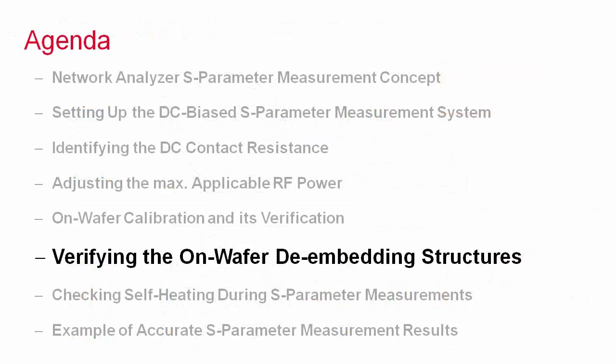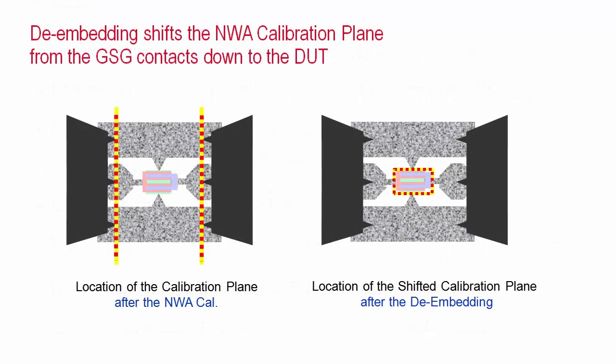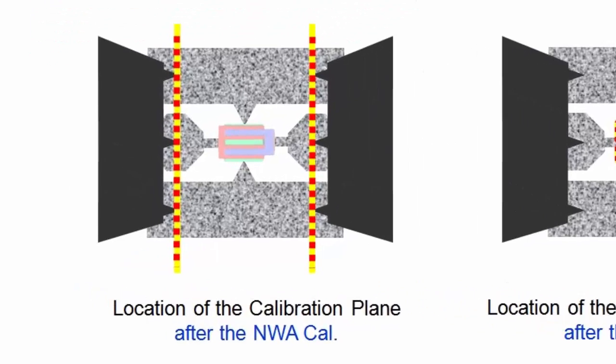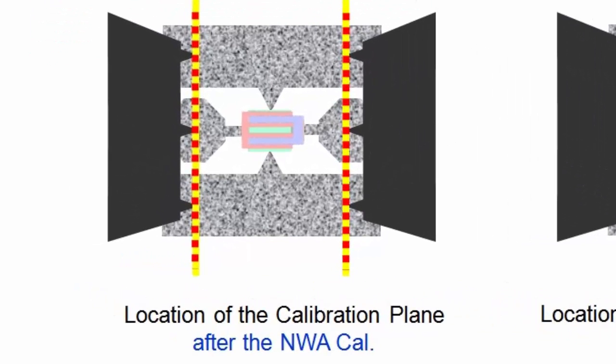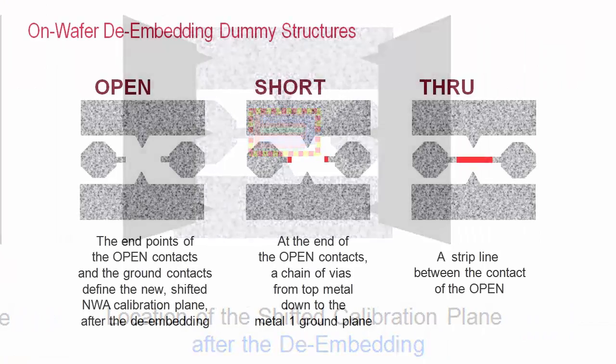The next step in our flow is the verification of the de-embedding structures. De-embedding means to shift the calibration plane from the GSG probe contact location down to the limits of the device model. A best practice verification is to have, besides the open and short on-wafer dummy, also a through dummy available which replaces the later DUT by a strip line.